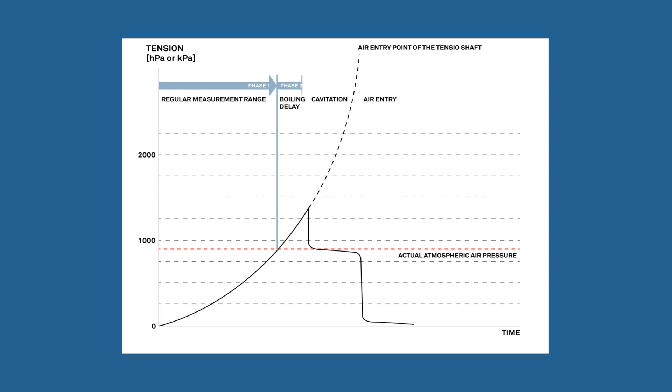Phase two: In the boiling delay phase, when the system is filled and completely air-free, the tension value rises up to the boiling delay area, which is above the ambient air pressure.